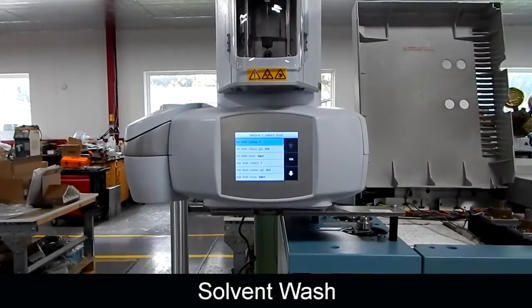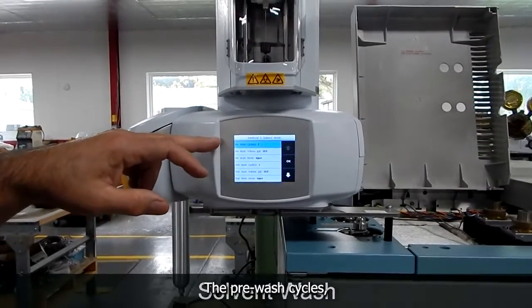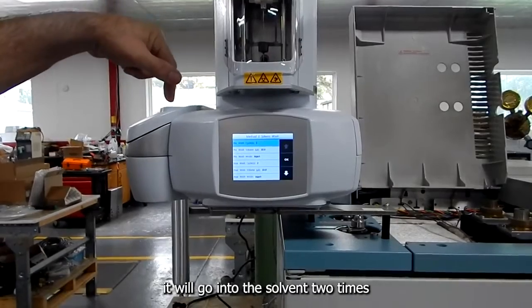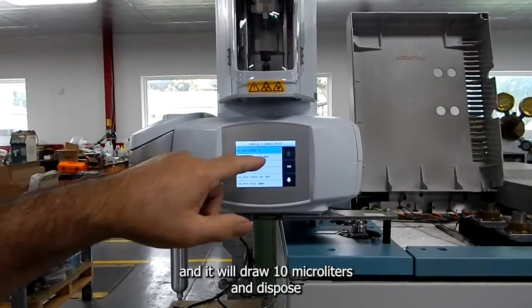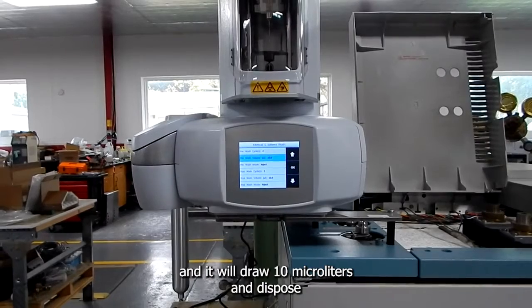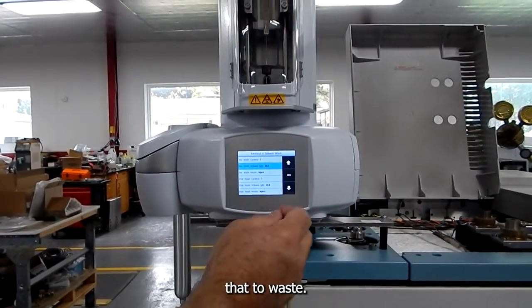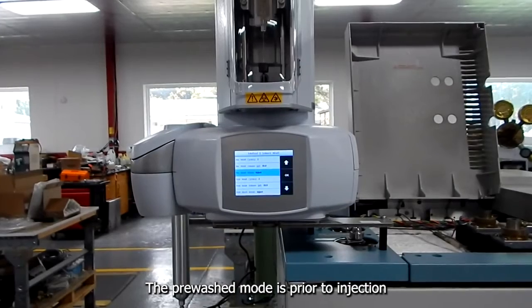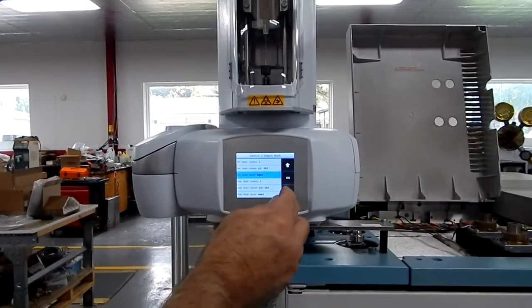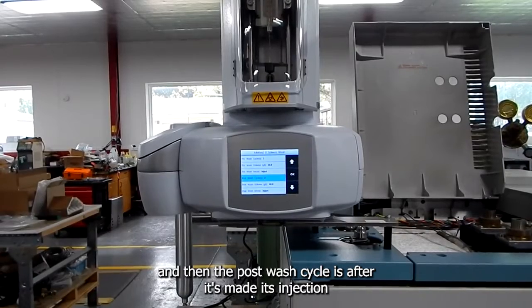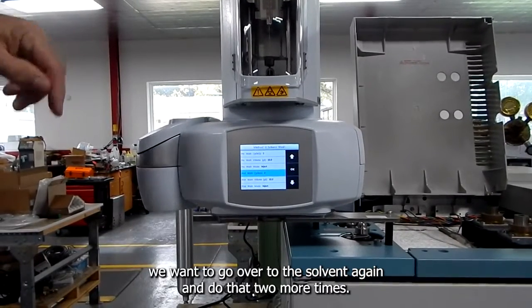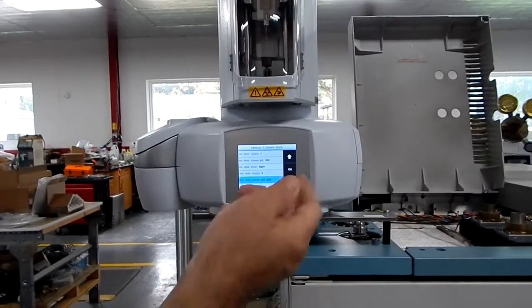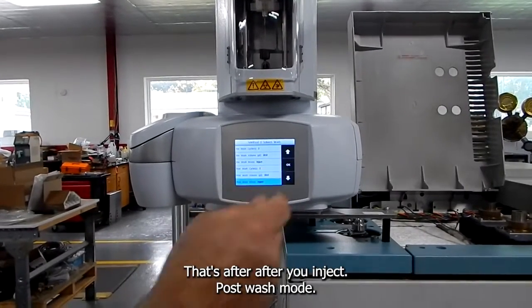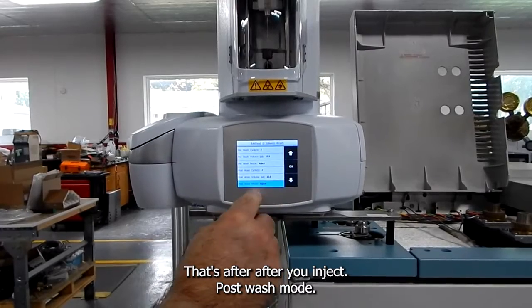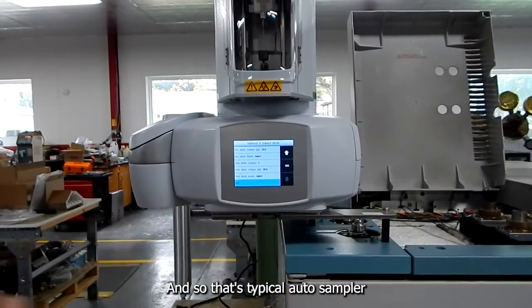solvent wash. The pre-wash cycles, it will go into the solvent 2 times, and it will draw up 10 microliters and dispose that to waste. The pre-wash mode is prior to injection. And then the post-wash cycles is after it's made its injection, we want to go over to the solvent again and do that 2 more times. 10 microliters, and that's after you inject, the post-wash mode.